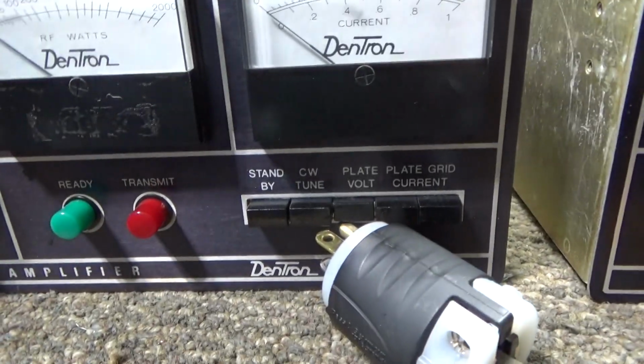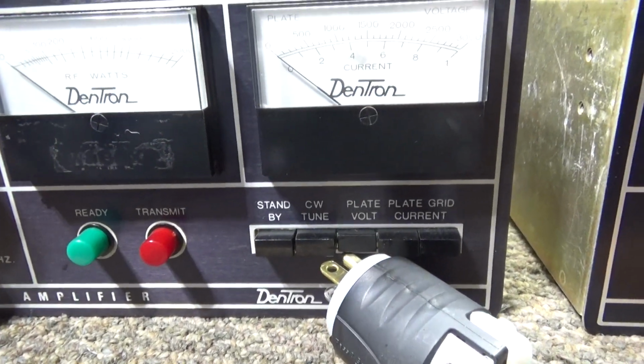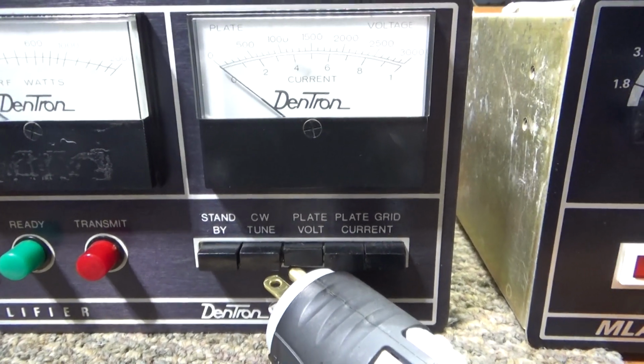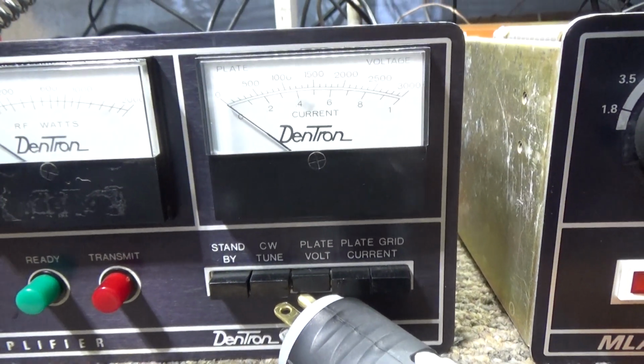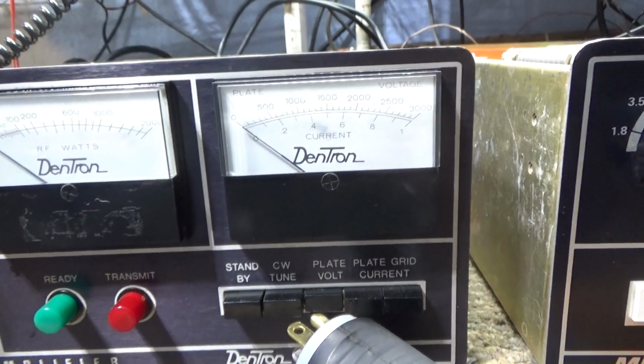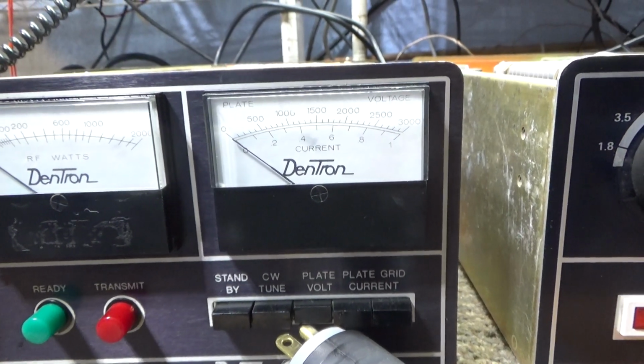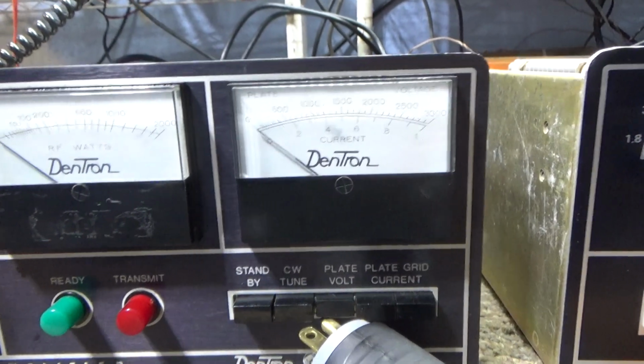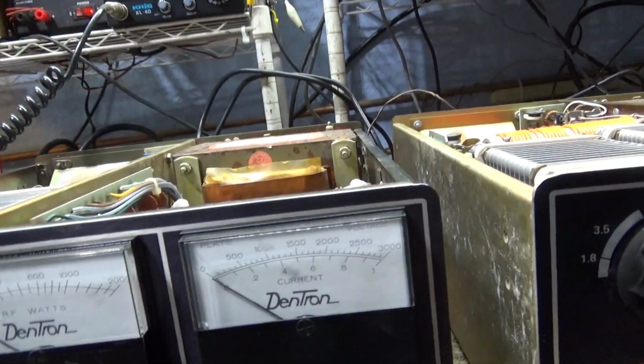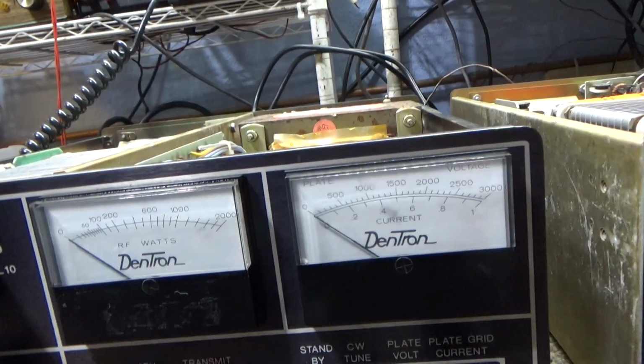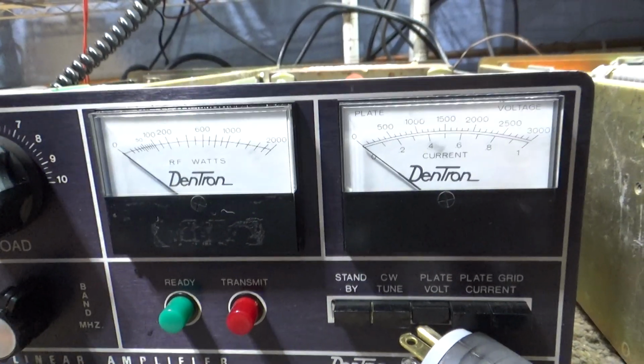So even if you have it on high, until that time delay kicks in, it's going to start at the 1800 volt tap, and then when that time delay kicks in, it'll jump up to the 2300. That's a poor man's soft start, because other than that time delay, it doesn't have a soft start in this amplifier.